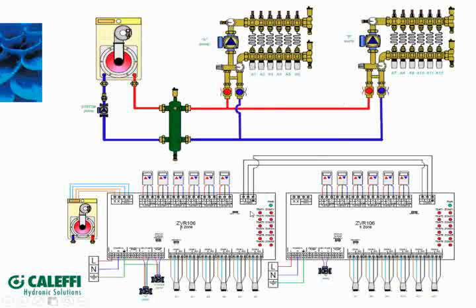But this way, you could think of this too. This could be zone valves, regular zone valves, and you can put multiple secondaries. Basically you got 6 zones per secondary pump that you could do then. But it will communicate back over there.